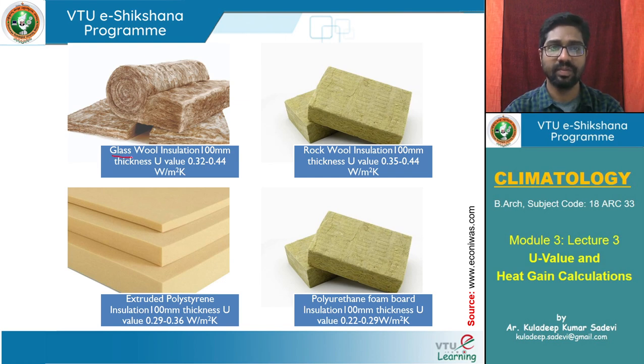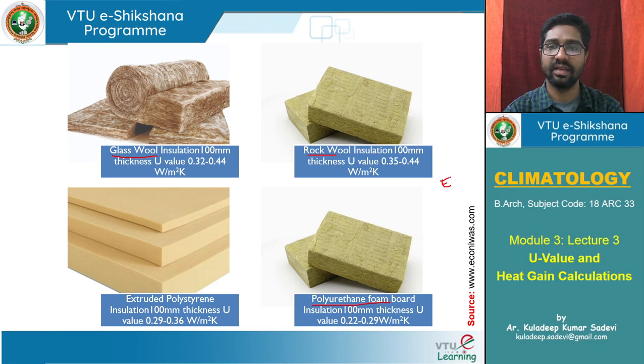The four insulating materials shown are: glass wool, rock wool, polyurethane foam board, and expanded polystyrene (EPS) — which is thermocol — along with extruded polystyrene (XPS). XPS is a better material especially for exterior applications, as it is not much affected by weather conditions or water seepage, whereas EPS can be affected.